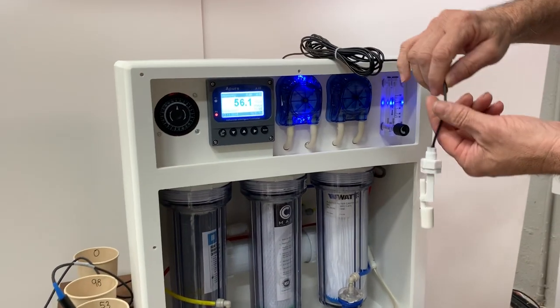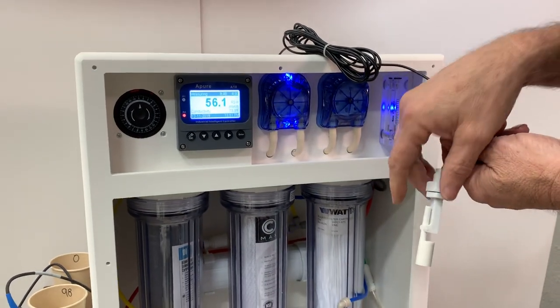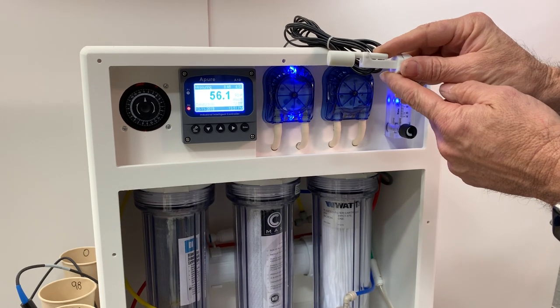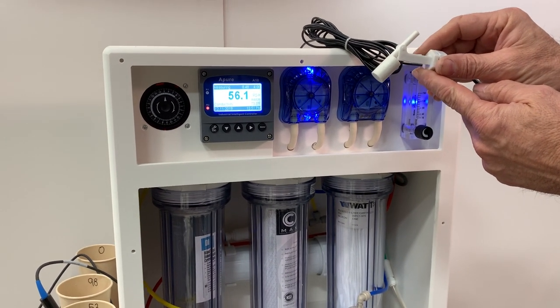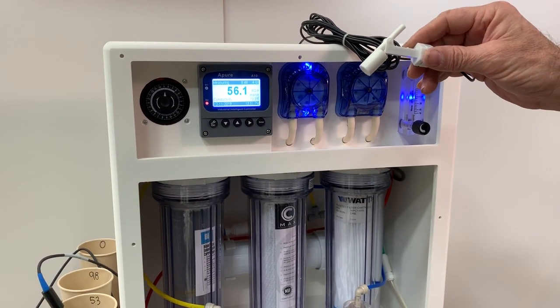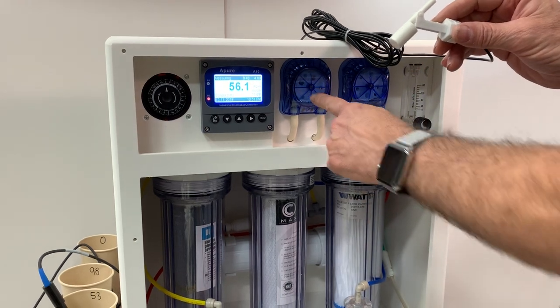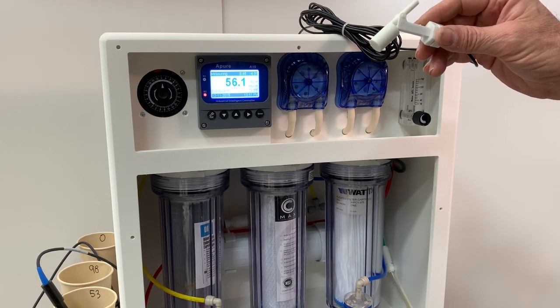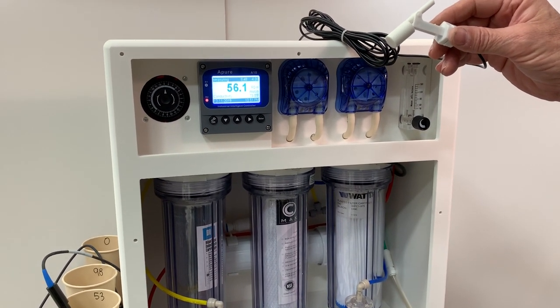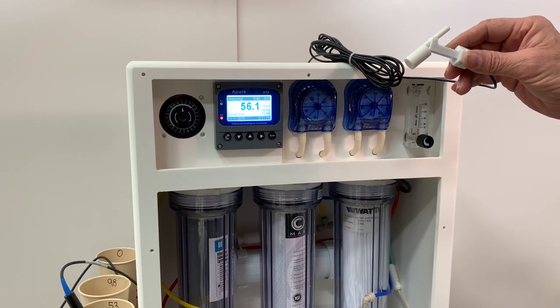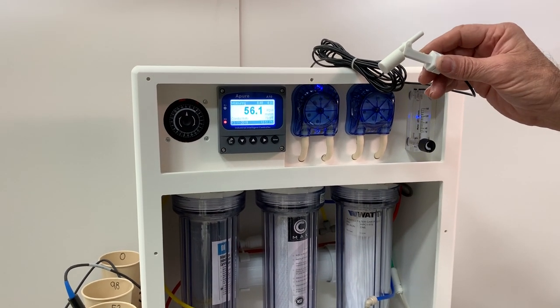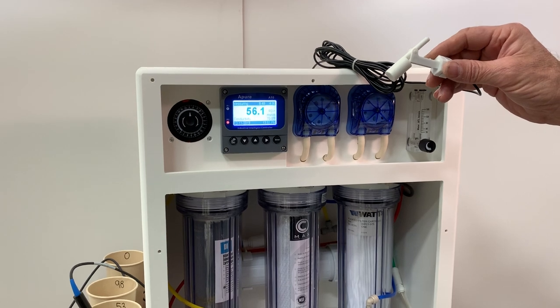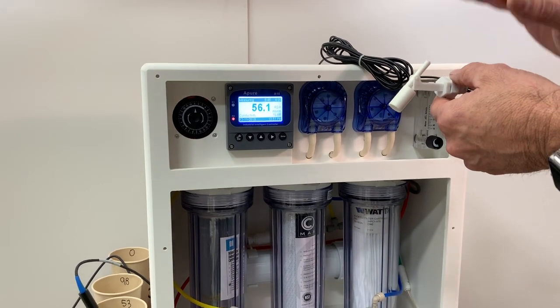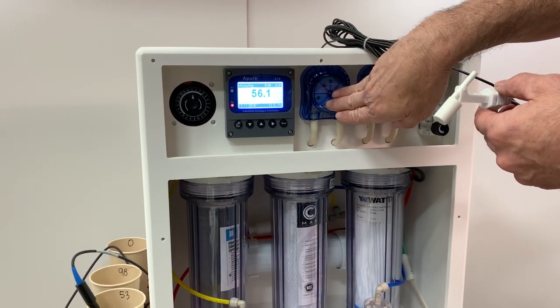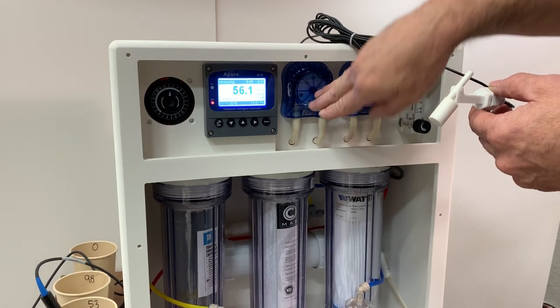The reason that the water is changing right now is because the float switch is satisfied. If this were to fall, there's a time delay built in, and it's going to turn off that water changing feature, because we don't want to take water out of the tank if the float switch is below the set point in your sump. So right now, what's happening is it has paused the removing of water.